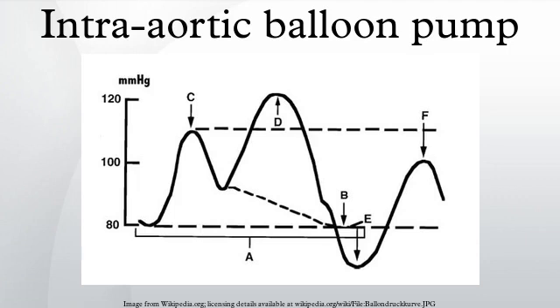It actively inflates in diastole, increasing blood flow to the coronary arteries via retrograde flow. These actions combine to decrease myocardial oxygen demand and increase myocardial oxygen supply. A computer-controlled mechanism inflates the balloon with helium from a cylinder during diastole, usually linked to either an electrocardiogram or a pressure transducer at the distal tip of the catheter.